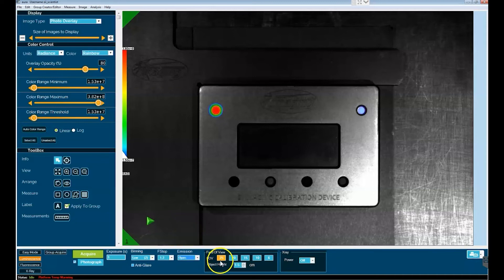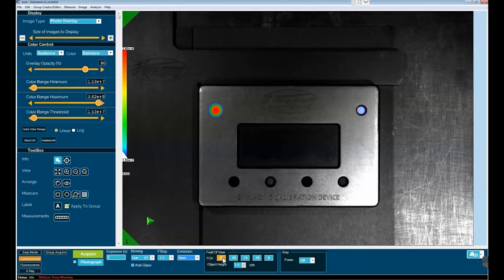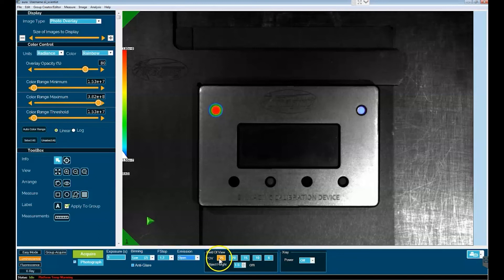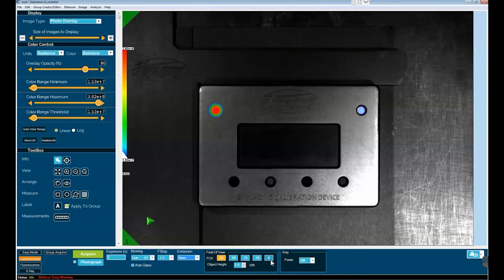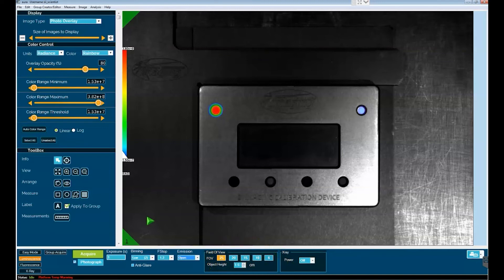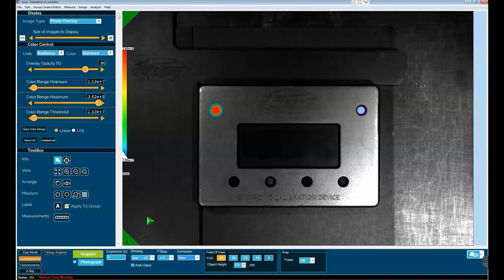Next are your field of view options. The maximum field of view that you can get on an Ami HTX is 25 by 17 centimeter square field of view, and that's what you're seeing here. You can go stepwise down from 25 by 17 all the way to 6 by 4 centimeters square. In this case you would be imaging not five mice at a time but typically just part of a mouse. Here the motivation at a small field of view is to get enhanced magnification which will provide greater resolution not only of the white light image of your target but also the optical data coming from it.